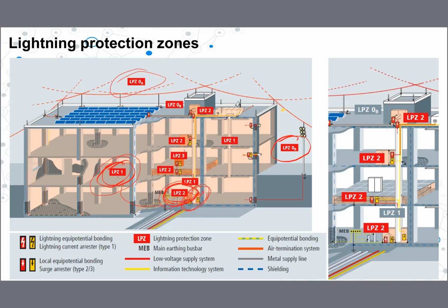So now you see this zone is zone 3. Here and here are almost the same, but here you have equipotential bonding, right? And it is more covered, therefore it is zone 3. So that's how we do the survey. Not just looking at the building orientation and building partitioning. You have to study how these equipotential bondings are there, how the lightning protection system conductors are installed in this building. By looking at the whole picture, the bigger picture and overall aspect of the lightning protection, only then can we decide, right? So that's why I show you this as well, right?